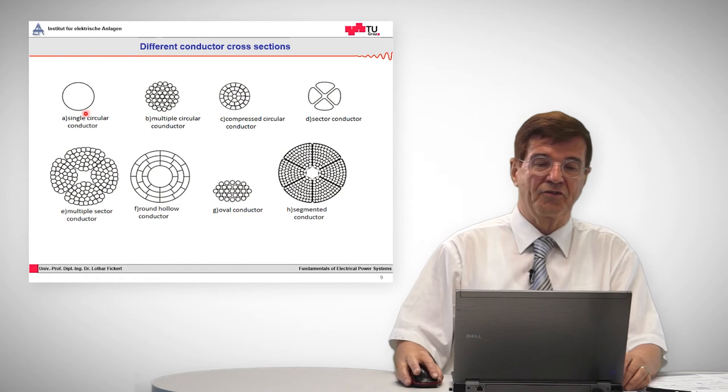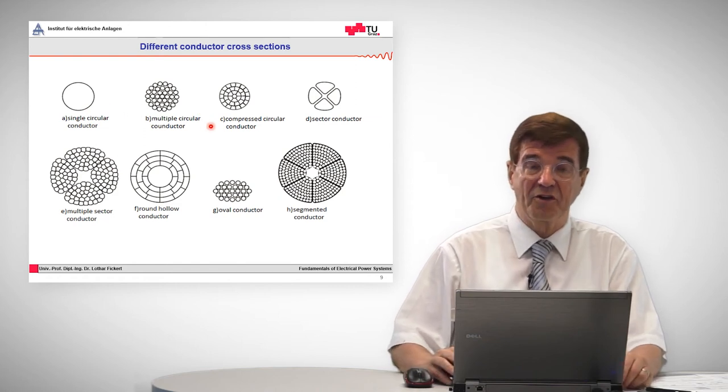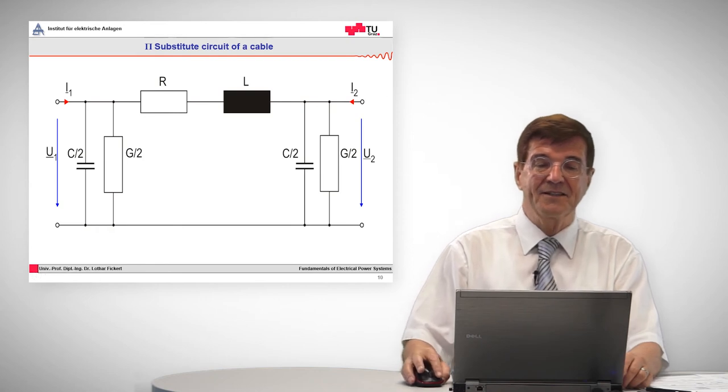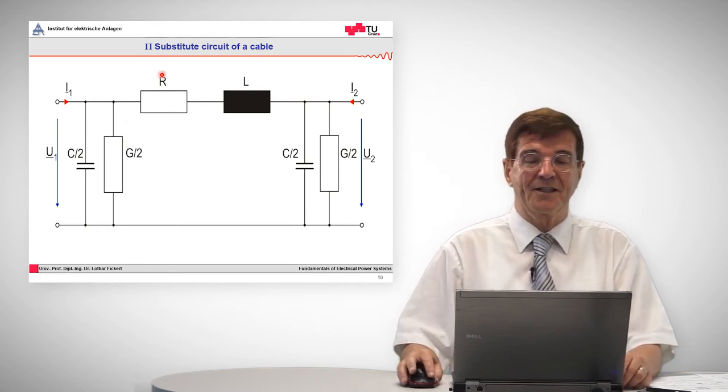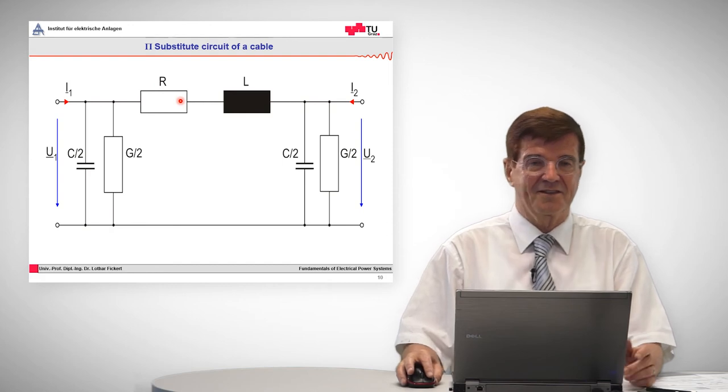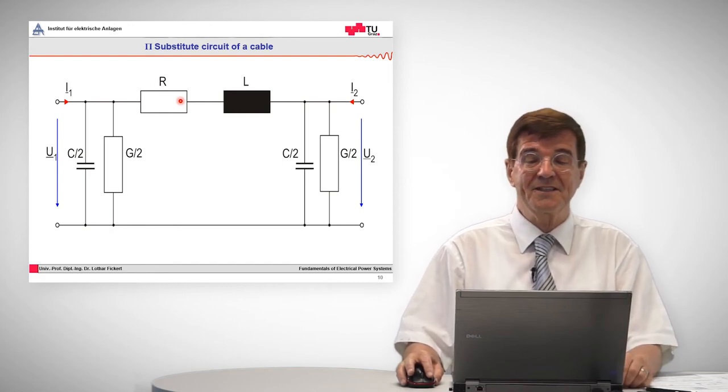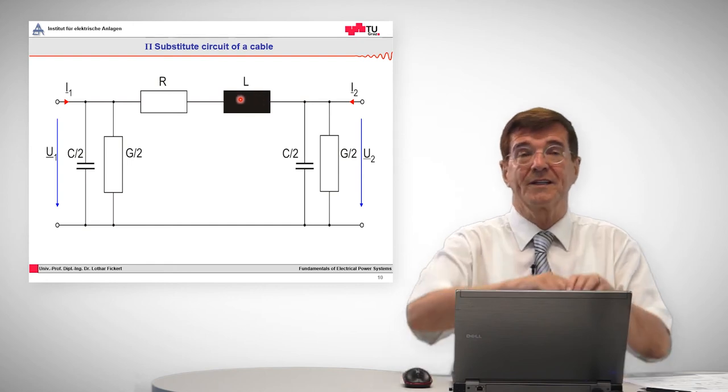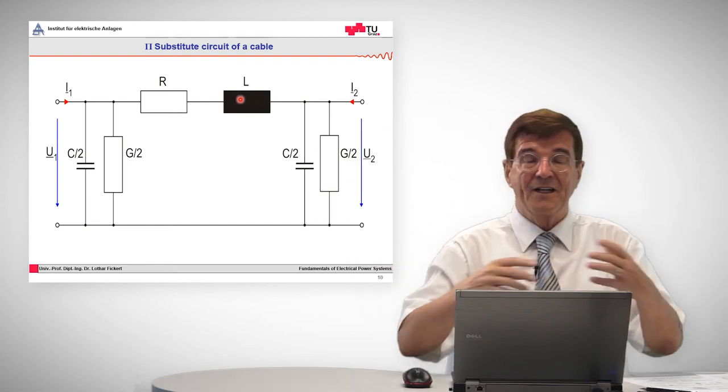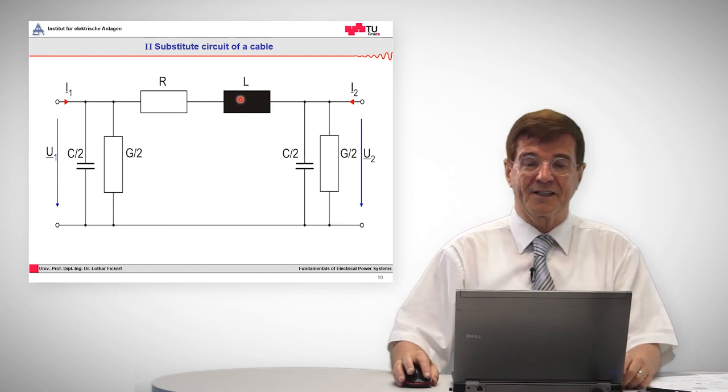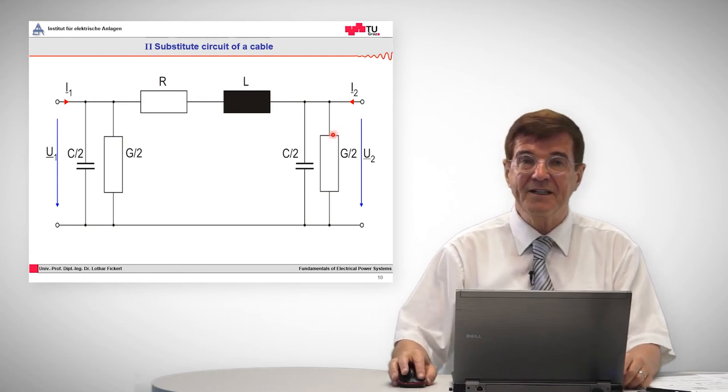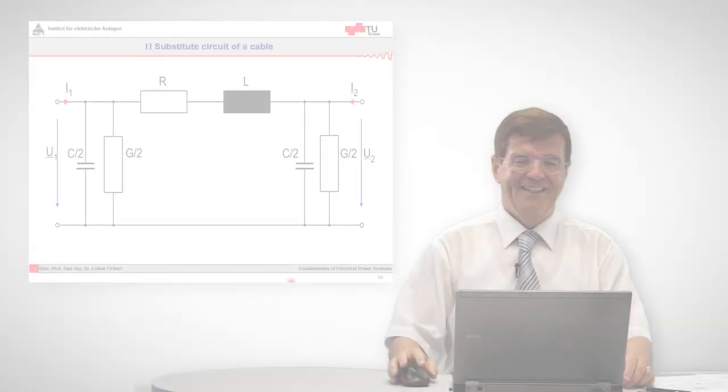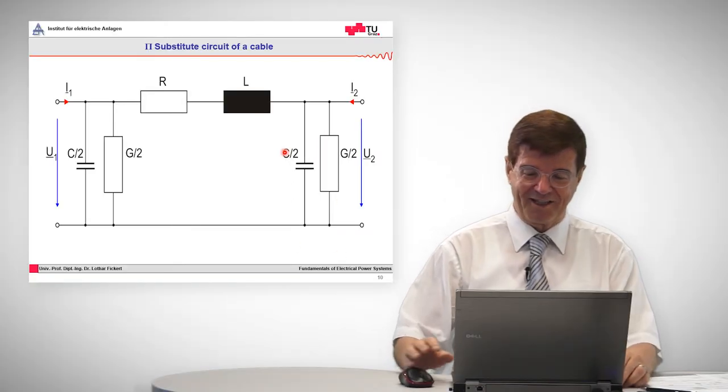These are the different cross sections, and this is the representative substitute circuit of a cable. A cable has a resistance that is the copper resistance or the aluminum resistance. Then it has an inductance because each loop, and the cable forms a loop, can be assigned to an inductance. Then we have some leakage resistances, for example bad insulation pieces, and then we have the capacities of the cables.